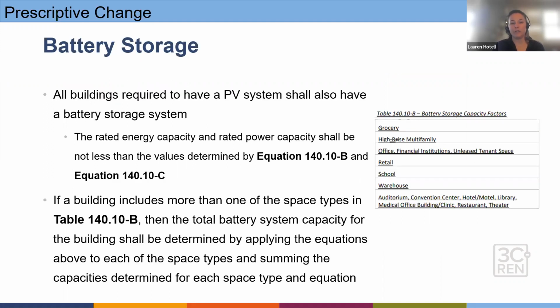Battery storage. Similar to the multifamily and single family, all buildings that are required to have a PV system also need to have a battery storage system. The two equations that we'll be using for that are rated energy capacity and rated power capacity. They need to be no less than the values that are determined by those equations.